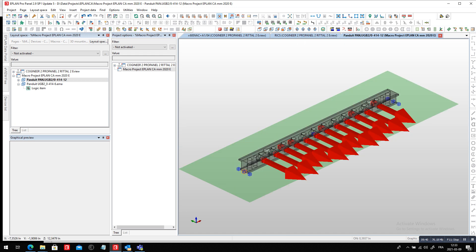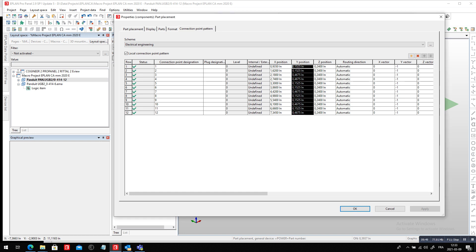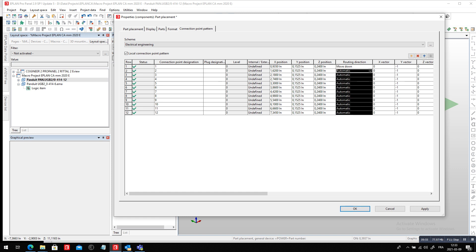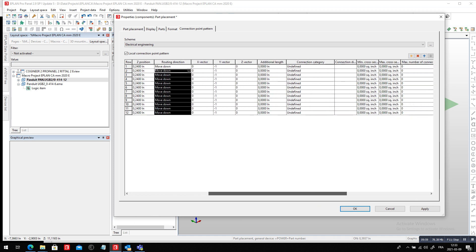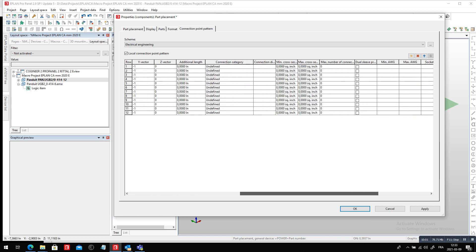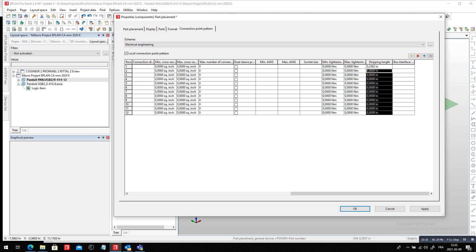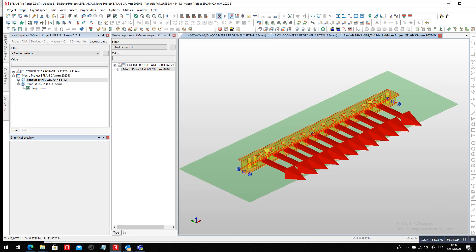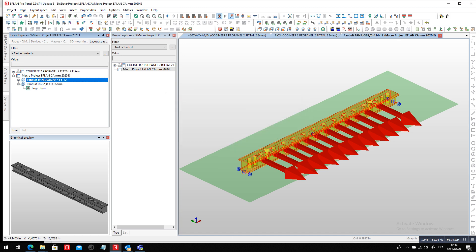And you can see that most of them are nicely connected. Maybe a few adjustments, maybe the depth here that has to be the same. The other thing is maybe where do you want to move this, move this down, copy and paste. And what you can also do is put some extra length if you want to, or some extra stripping length. It's all possible here. You can say, let's add 0.25 inch for stripping, or you can even go with six millimeters. So this is basically what I do. So six millimeters converted. As you can see, I don't have to really do a calculation. Then it's the minimum gauge is 14. It goes to four. That's the biggest one I can copy and paste. This is basically the min-max connection points that can be connected to this. This is pretty much what we do here at the connection points. And when you're finished, you just generate the macro itself.